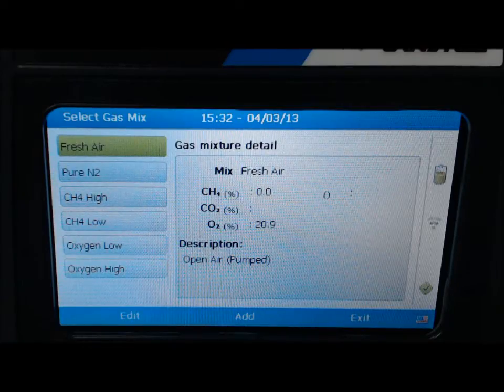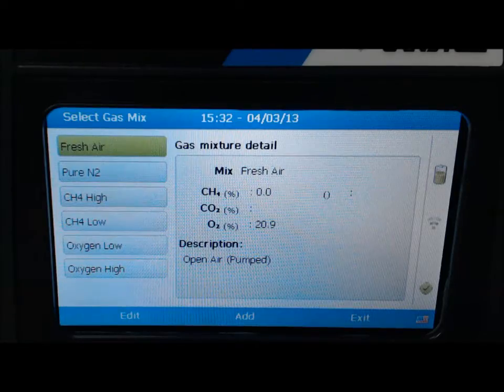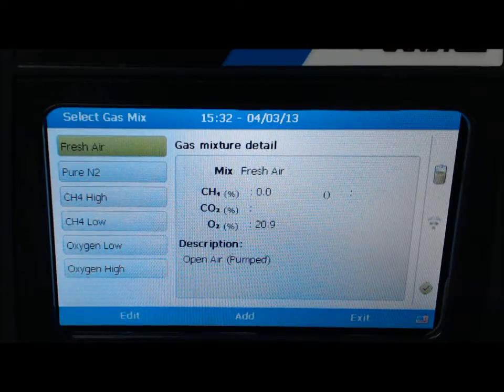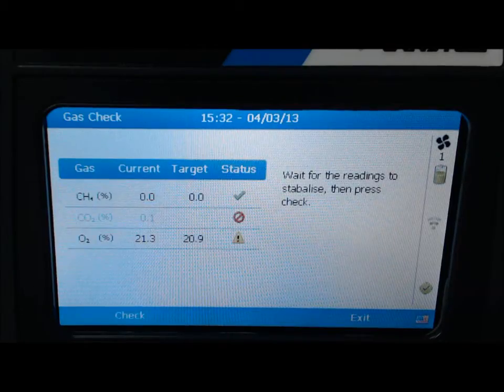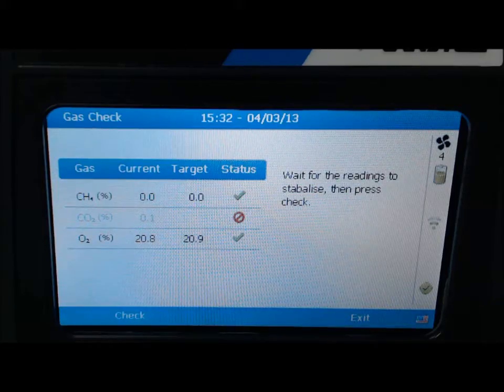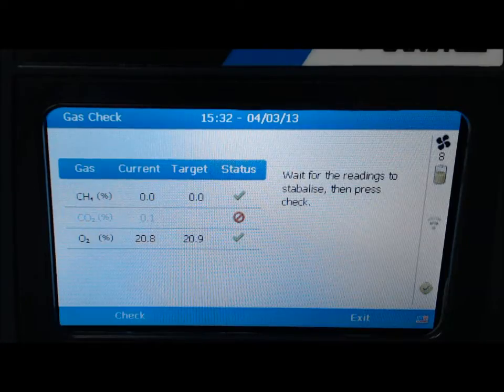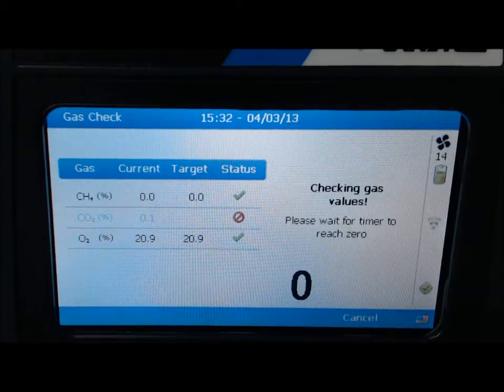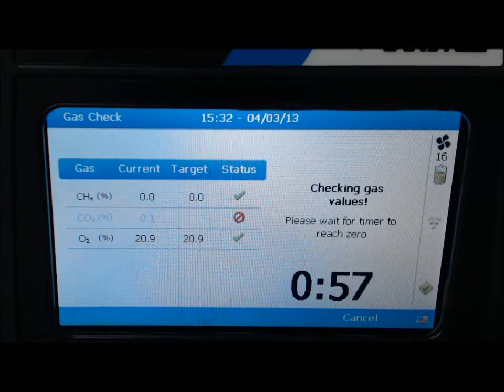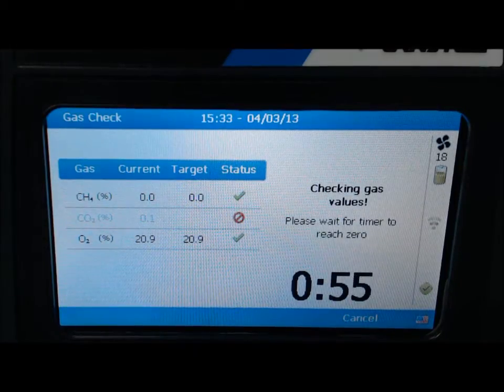Using the arrow keys, select fresh air to zero the methane channel and press enter. This will take you to the gas check screen and the pump will automatically turn on. Select check when readings have stabilized. A 1-minute timer will start for readings to stabilize.